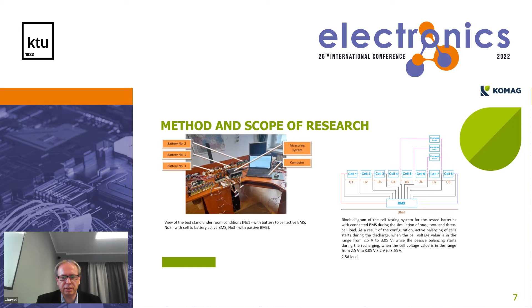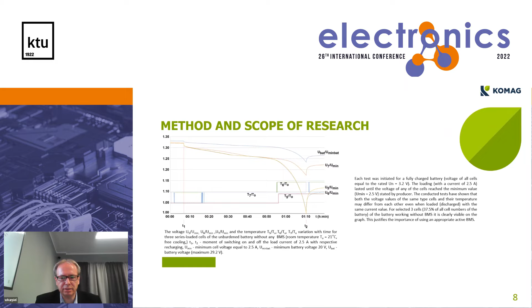The loading continued until the voltage of any of the cells reached the minimum value stated by the producer. The tests carried out have shown that both the voltage values of the same cells and their temperature may differ from each other even when loaded with the same current value. For the selected three battery cells operating without a BMS system, this is clearly visible in the diagram. Therefore, an active BMS system should be used.